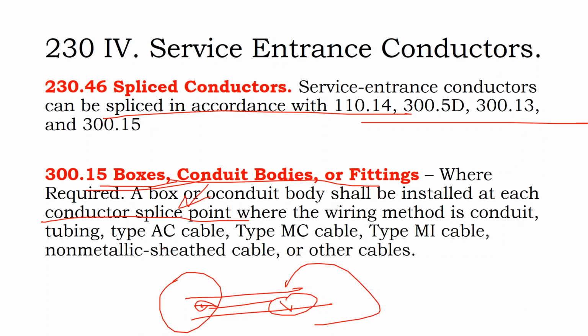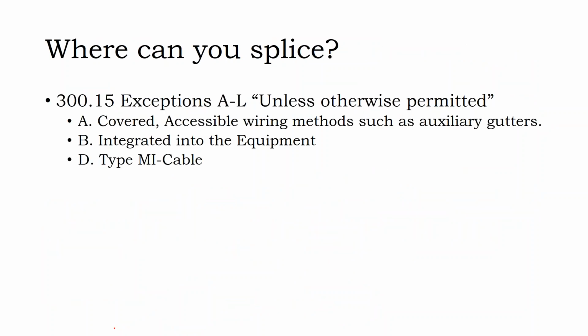And so that very easy tool that you can use for splicing cables together that you can find at Home Depot is not listed for service entrance conductors, so it cannot be used on your solar array. It's not listed for feeder conductors. It cannot be used on your solar array. Unless it was listed, and then it could be used.